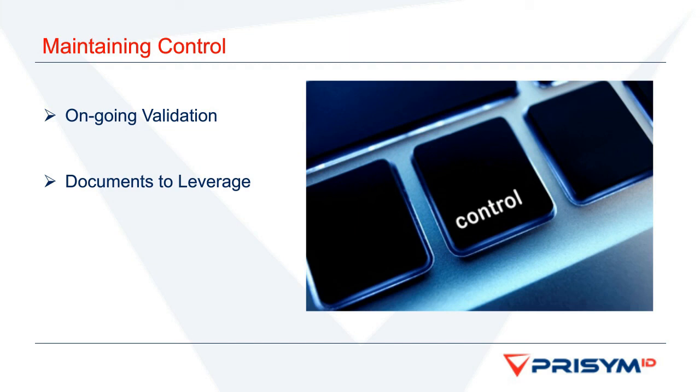These documents could contain a functional testing of the patch or release with an amount of regression testing to show that the existing functionality has not been adulterated. This could be used in the gap analysis to determine what testing should be performed by the regulated company. For example, the functional testing has been performed by the supplier with the relevant objective evidence. Therefore, from a risk-based approach, business case testing as described in the validation master plan to establish that the new functionality operates as described and that the existing processes have not been adulterated.